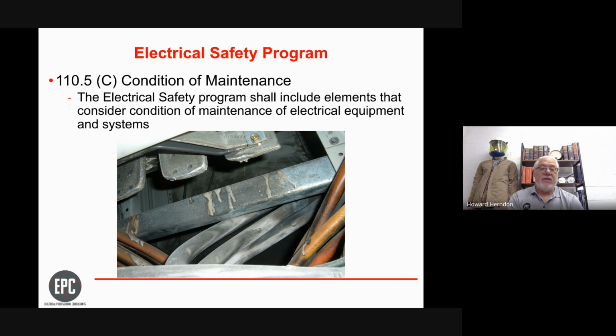And you can see from the bussing there, those are 3 pieces of electrical bussing. It's aluminum bussing. That aluminum bussing melts at about 1250 degrees. And you can see droplets that have dropped down on those conductors. Now, those conductors are not naturally smoky. They just have gone through an arc flash event. And the outside of this enclosure was perfectly clean. The equipment was less than 5 years old.